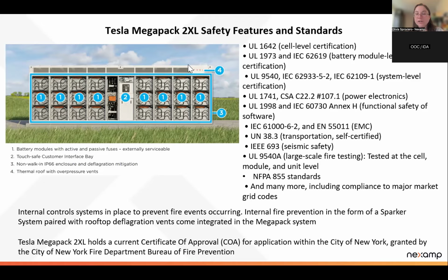The reason you don't want to suppress too much is, for one, the water introduces oxygen, but also if you were to use an aerosol system or some chemical suppressant, if you're not entirely sure the fuel has been burnt through and you leave a little bit of fuel left, it's more dangerous for the chance that it might reignite than to just let it burn and stabilize itself.